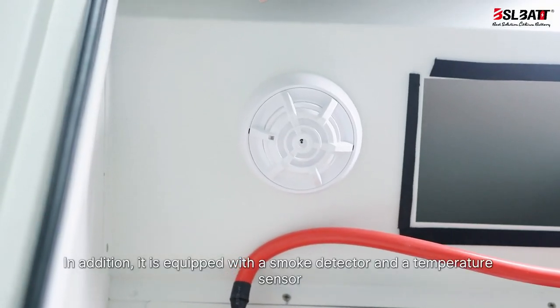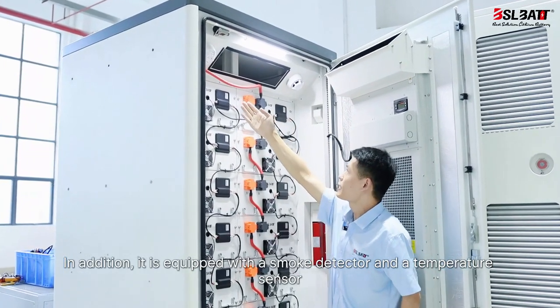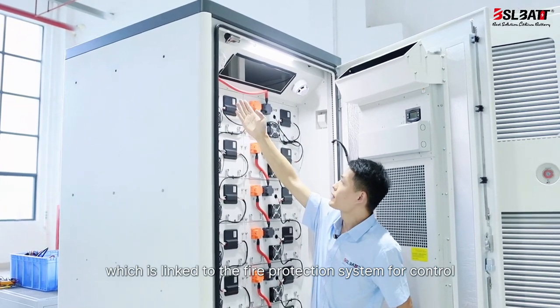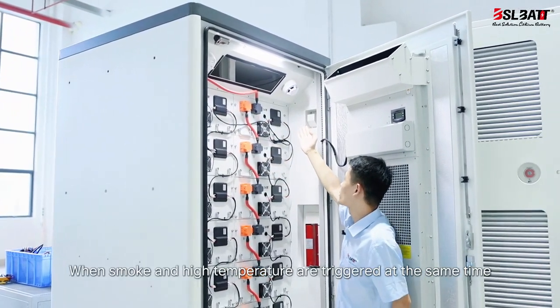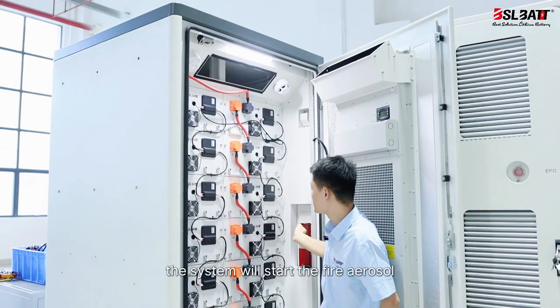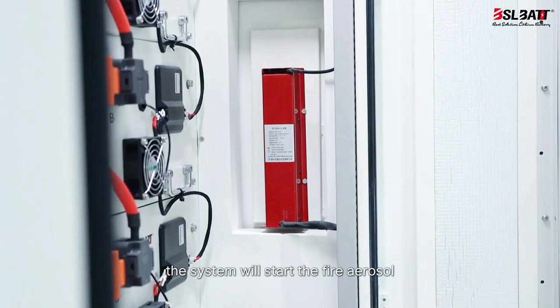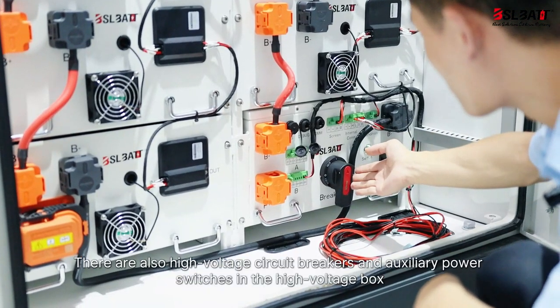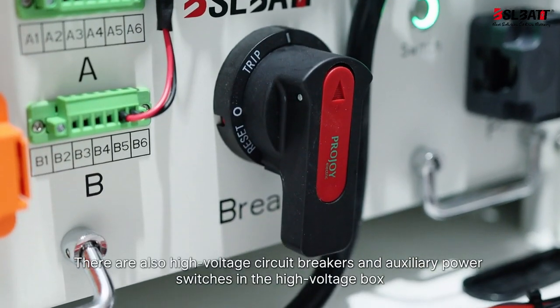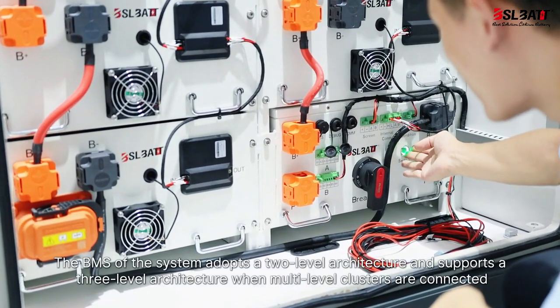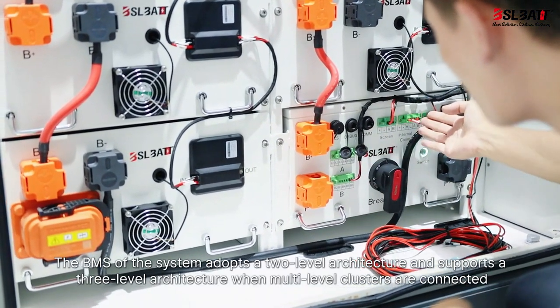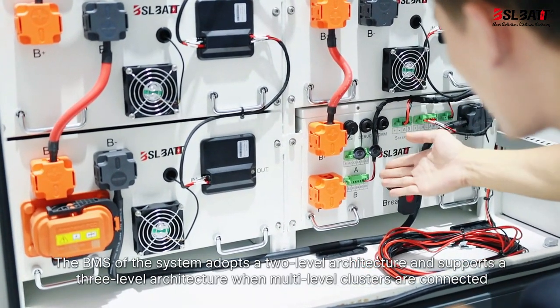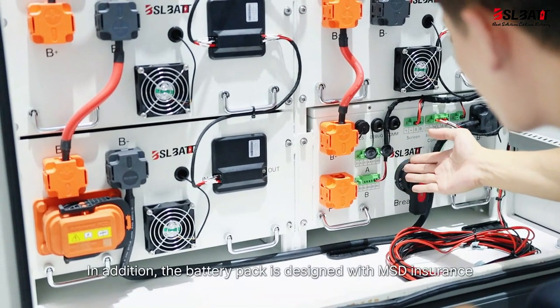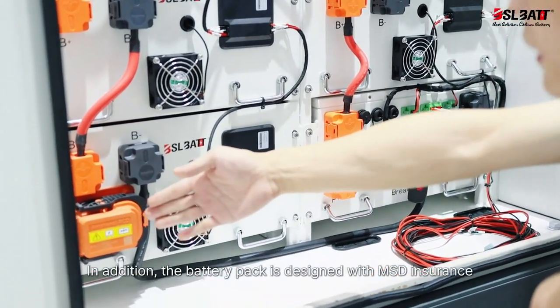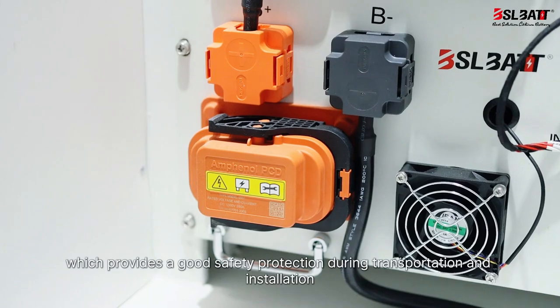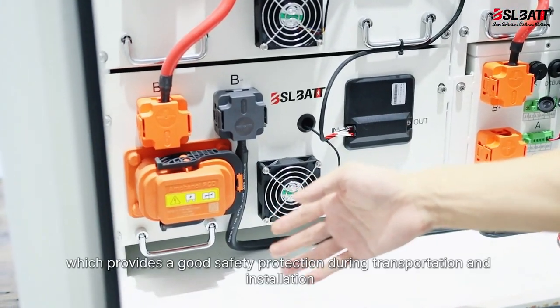In addition, it is equipped with a smoke detector and a temperature sensor, which is linked to the fire protection system for control. When smoke and high temperature are triggered at the same time, the system will start the fire aerosol. There are also high voltage circuit breakers and auxiliary power switches in the high voltage box. The BMS of the system adopts a 2-level architecture and supports a 3-level architecture when multi-level clusters are connected. In addition, the battery pack is designed with MSD insurance, which provides a good safety protection during transportation and installation.